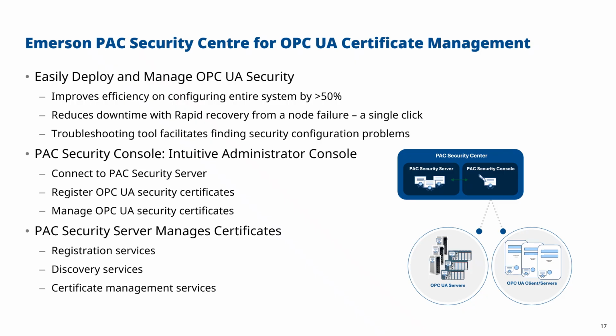It's based on a PAC Security Console, an intuitive administrator console that connects to the PAC Security Server. The PAC Security Server securely contains all of the certificates, and the PAC Security Console allows you to register and manage those security certificates. That includes securing them in a secure location, copying them to the right locations, and even revoking certificates—for example, if you change a CPU, if a user leaves, or if a node is decommissioned. So it includes various server management functions for certificates, registration, discovery, and certificate management services, all simplifying OPC-UA certificate management for non-IT type users.